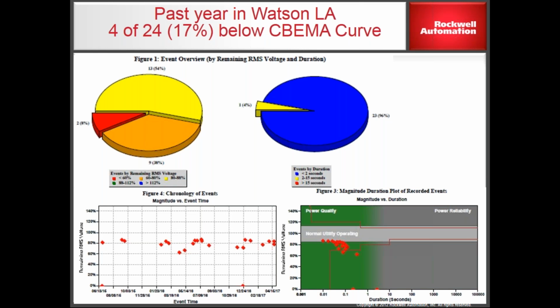On the left-hand side, what we're seeing is the magnitude of the event, meaning how bad was it. The ones in yellow, more than half of these events, were not likely to have caused downtime. They happened, but we rode through them - the equipment had enough ability to do that. The other half of the events are split into 2 groups, the largest of which are the ones that drop between 60 and 80% remaining.